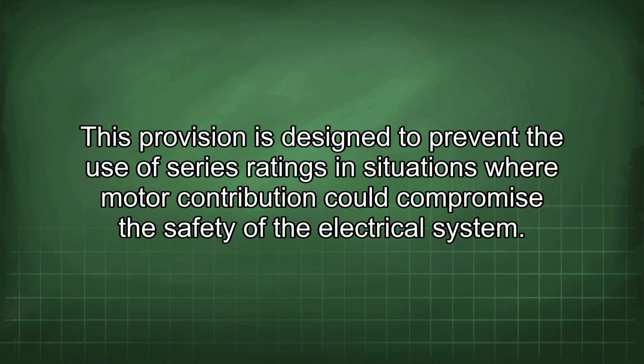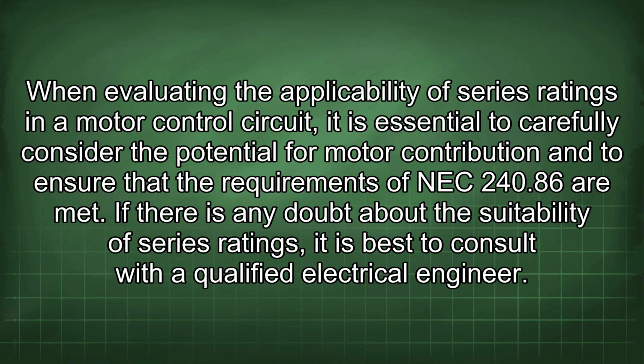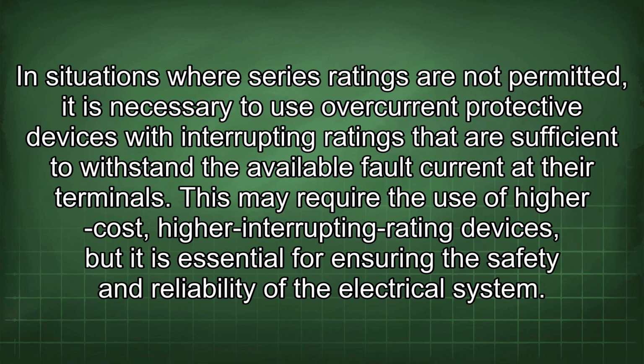of the electrical system. When evaluating the applicability of series ratings in a motor control circuit, it is essential to carefully consider the potential for motor contribution and to ensure that the requirements of NEC 240.86 are met. If there is any doubt about the suitability of series ratings, it is best to consult with a qualified electrical engineer. In situations where series ratings are not permitted, it is necessary to use overcurrent protective devices with interrupting ratings that are sufficient to withstand the available fault current at their terminals. This may require the use of higher cost, higher interrupting rating devices, but it is essential for ensuring the safety and reliability of the electrical system.